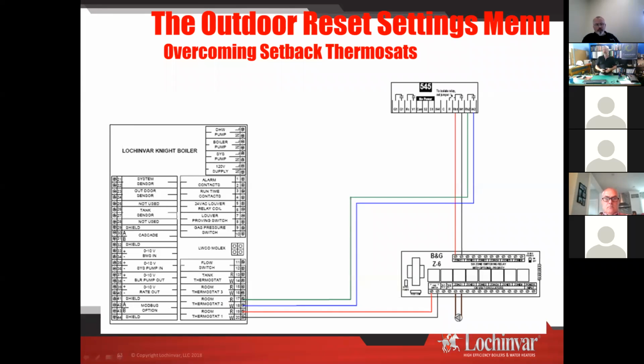Most often I've used that in cases where it is in churches. It's the most common spot that I've used that. And we'll use it in this, might be the sanctuary here on room thermostat 1, and we're running hydrowares, and all we want to do is keep the frost off. You don't want to make all the critters happy by making it so warm in the sanctuary they're coming in, but maybe they keep it at 50 degrees. And then come Sunday, they want to bump up the temperature. Well, that's this call here. That's maybe always 170 no matter what. So when that 2-stage thermostat says it's Sunday morning, crank it up, the boiler automatically raises its temperature. So it's kind of a cool feature. It's there.